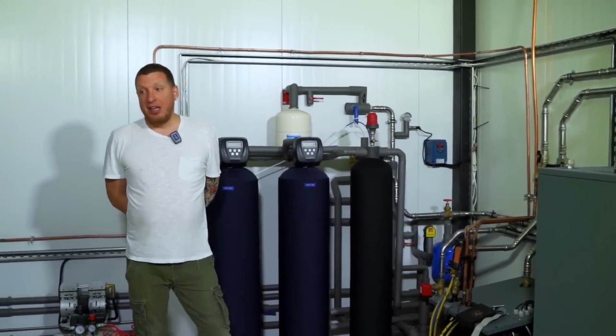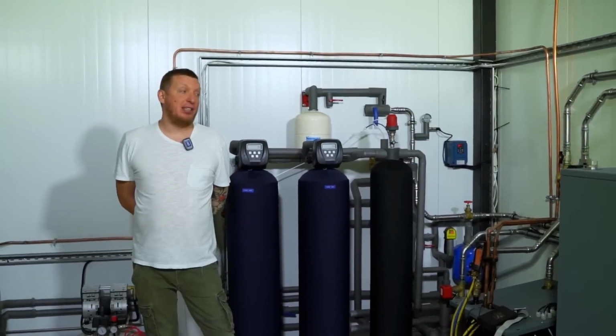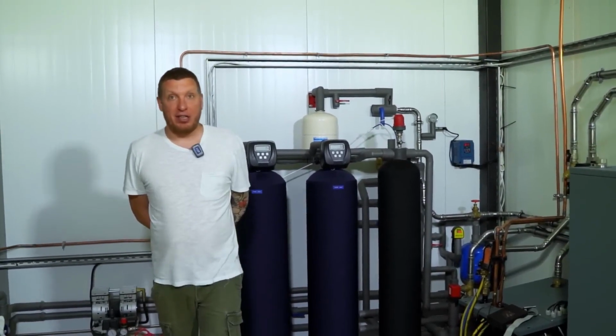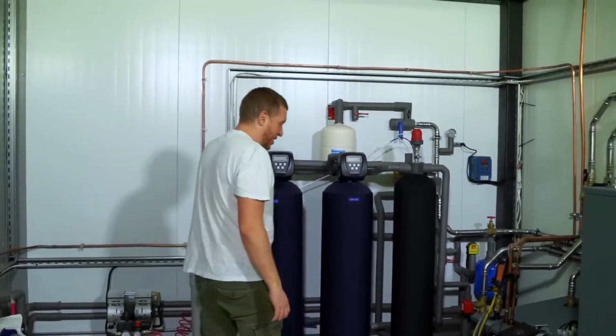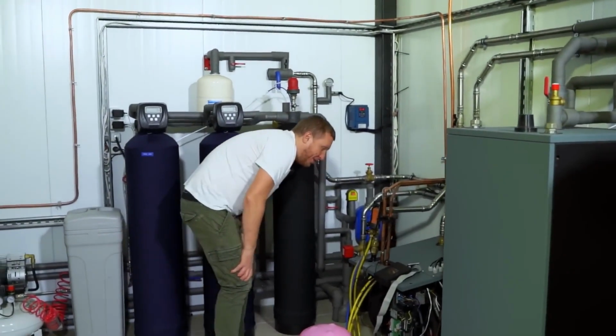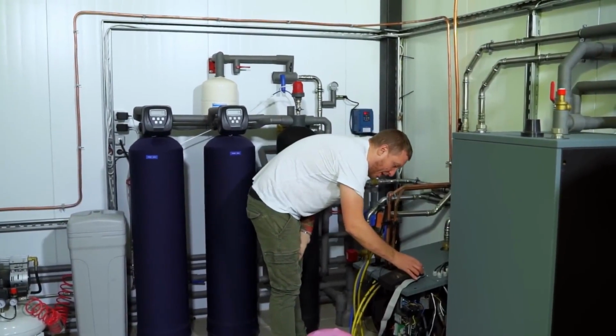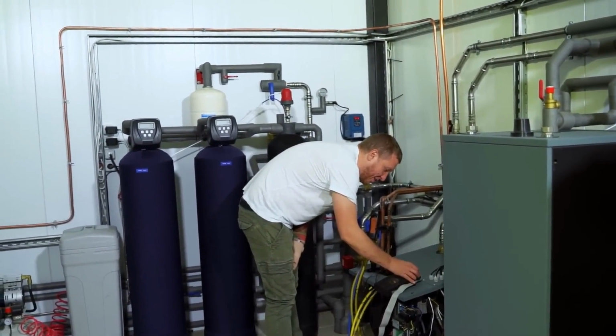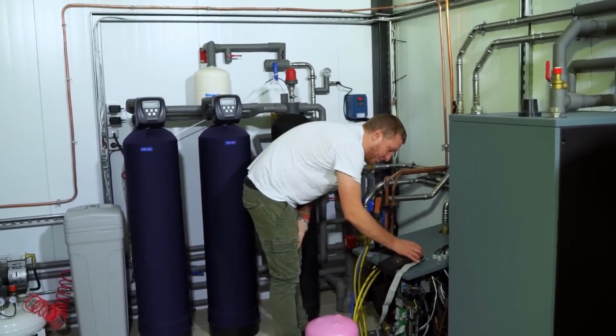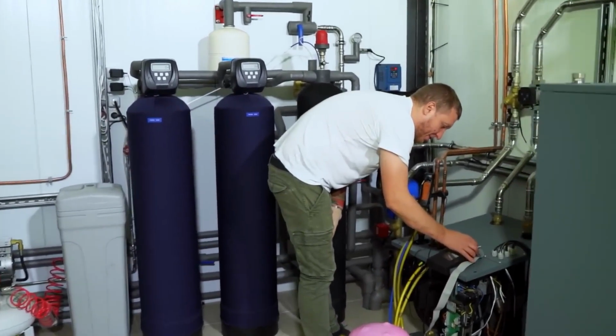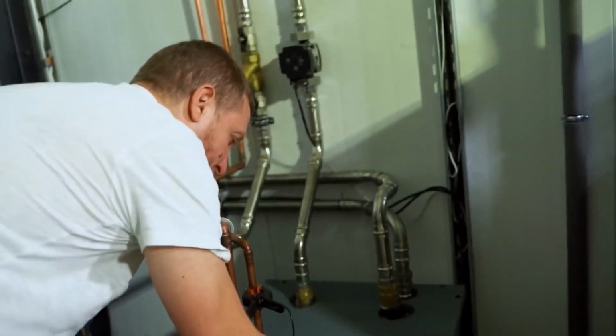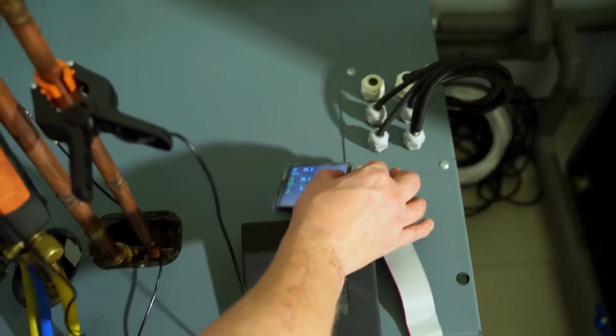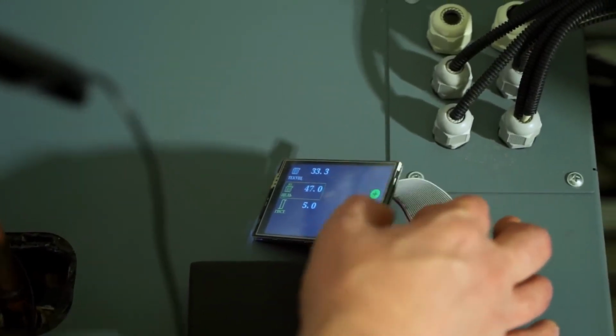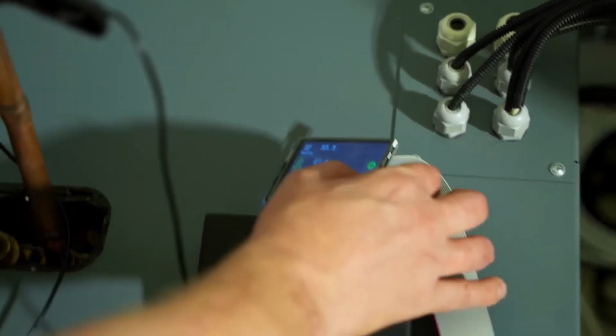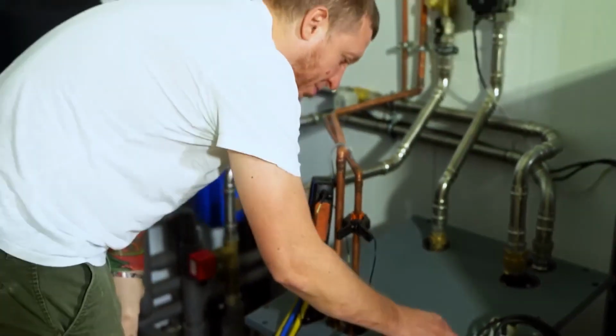So basically, this means the refrigerant is in a superheated state. And subcooling is when the temperature of the refrigerant at the condenser outlet should be at a certain value, but it's actually colder by a certain range. That's how it works. We've achieved these parameters. Now we're switching to maximum speed. All right, we need to do it this way. Let's set it so the temperature is higher. Otherwise, it's running at minimum right now. Set the target higher, and it will start ramping up the compressor. It's going to get really loud now, but that's okay.